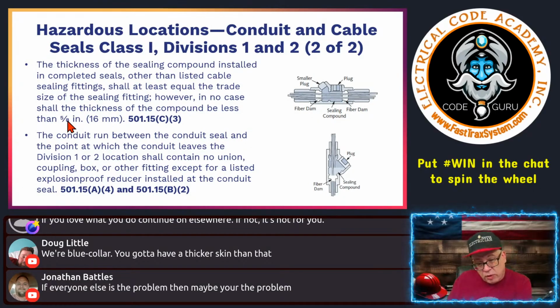So exam question: what's the thickness? The maximum thickness, it doesn't have to be what? It has to be equal to the trade size of the thickness, meaning it has to fill up the whole orifice, or shall be the thickness of the compound, but it can't be less than 5/8 of an inch in thickness. I don't know how you measure that, but it is what it is.